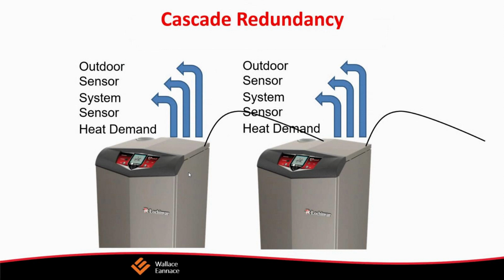It has a connection for a boiler pump, a system pump, the domestic hot water pump for an indirect, and then also a recirc pump. It comes with automatic freeze protection. When the temperature drops, it'll automatically go into low fire to maintain a sufficient temperature. It has runtime and alarm contacts. Once again, like you saw before with that yellow screen over there, letting you know that it's been running for too long and it needs service.